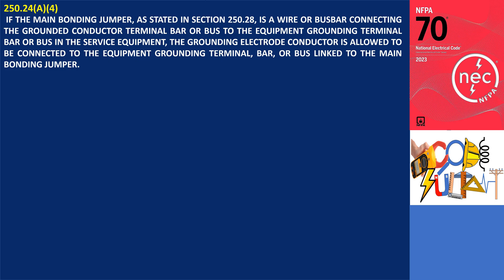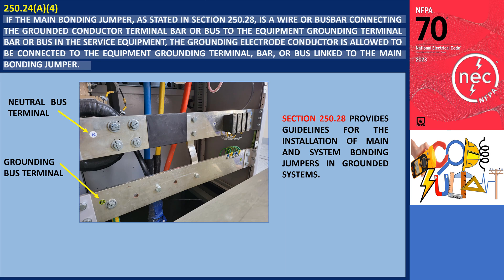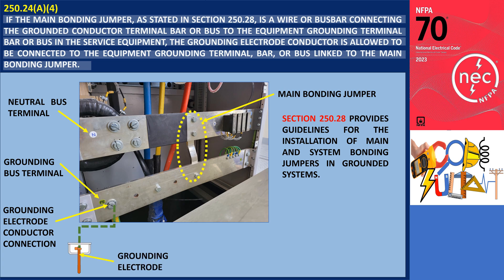Section 250.24(a)(4) specifies that if the main bonding jumper, as stated in Section 250.28, is a wire or bus bar connecting the grounded conductor terminal bar or bus to the equipment grounding terminal bar or bus in the service equipment, the grounding electrode conductor is allowed to be connected to the equipment grounding terminal, bar, or bus linked to the main bonding jumper. The provided image depicts a neutral and grounding bus terminal in a low-voltage switchgear where a bus bar serves as the main bonding jumper, and it is allowable to connect the grounding electrode conductor to the equipment grounding terminal, bar, or bus associated with the main bonding jumper.